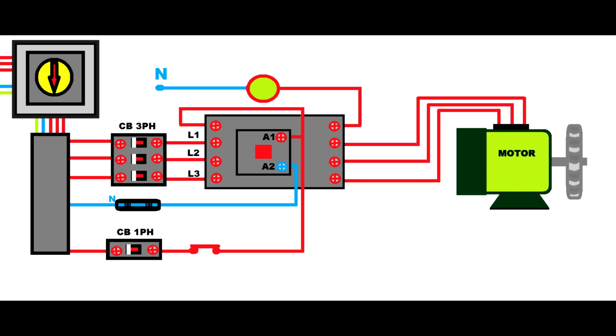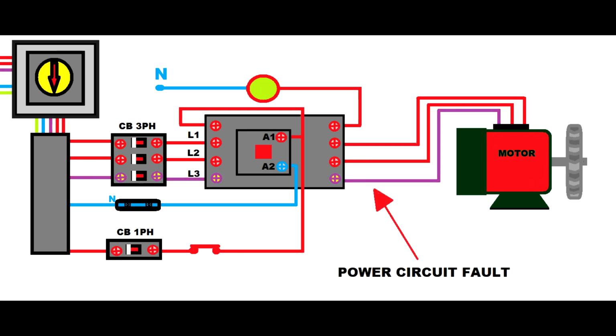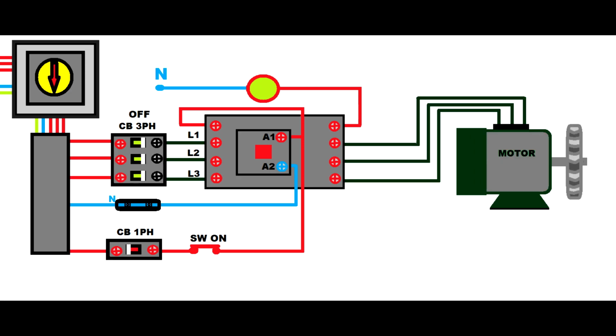Up to here, the customer is delighted. It saved a lot of money, but this is a shortcut. I don't like this job. If you have a mechanical failure in the motor, maybe you'll have an unbalanced phase due to a loose connection between the contactor and the motor, or maybe between the circuit breaker and the contactor, anywhere, there won't be any overload protection to turn the motor off in time. Finally, if the running amps go too high, the circuit breaker will turn off the circuit. But by that time, the motor could already be burned.